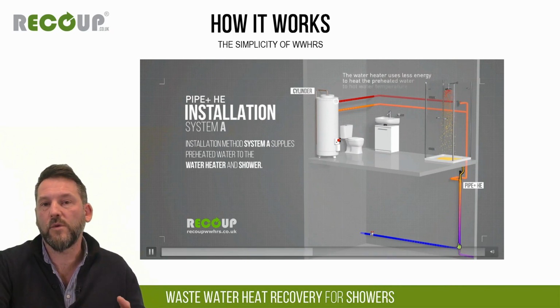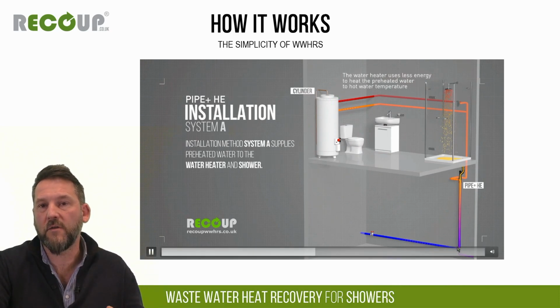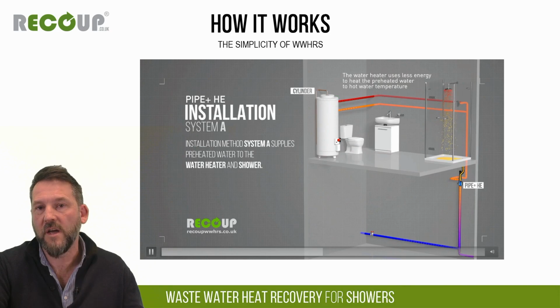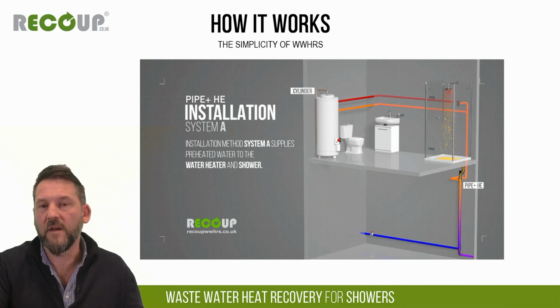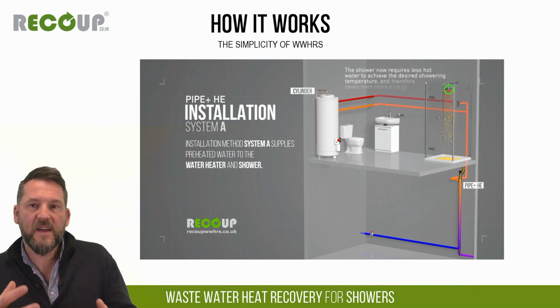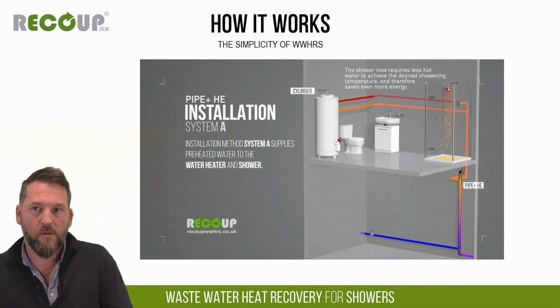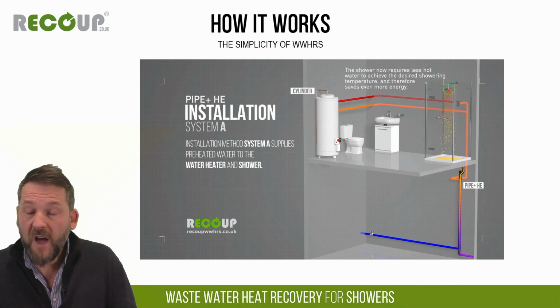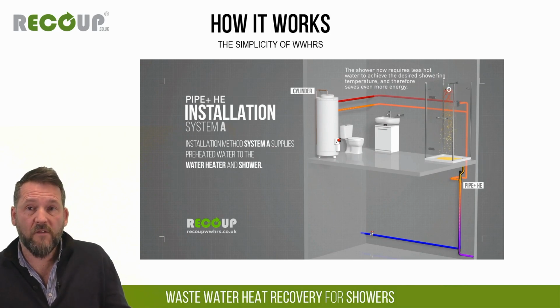So if that cold water feed's coming in at around 10 or 12 degrees, the cold water is then preheated, so that will go around the outside of the heat exchanger and is preheated up to about 25 to 28 degrees. So immediately you can see we're getting a big free energy uplift from that outgoing wastewater. And that's the basic premise of wastewater heat recovery. It's a simple heat exchanger technology.